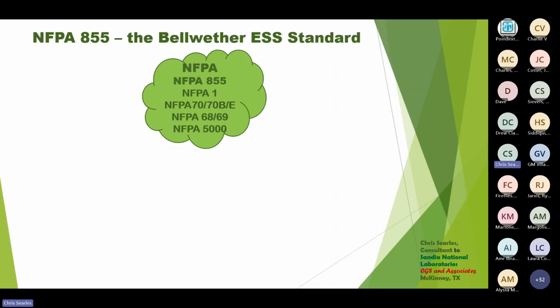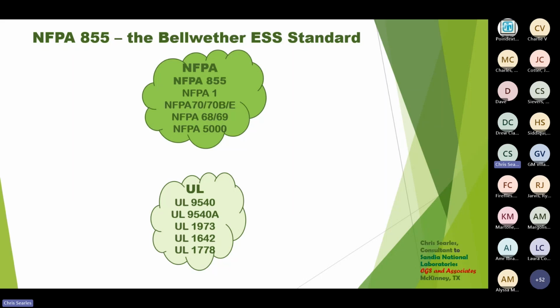Then we have two codes that are now part of the 855 standard, NFPA 68 and 69, which deal with explosion control and making sure there's a ventilation configuration that gets rid of toxic gases. But there are some other elements we'll talk about in a minute. NFPA 5000 is the equivalent for NFPA to the International Building Code, but it plays a much more minor role. Then within UL 9540, it points to a number of other standards.